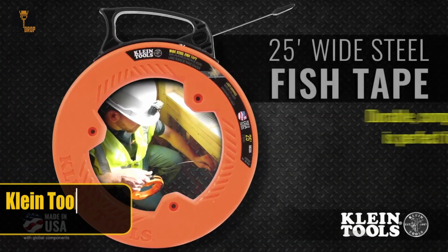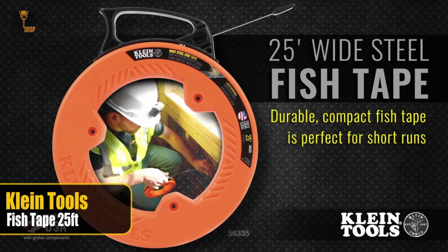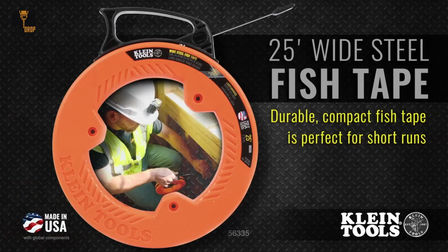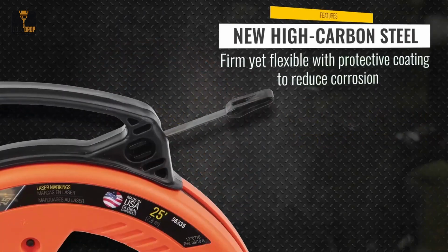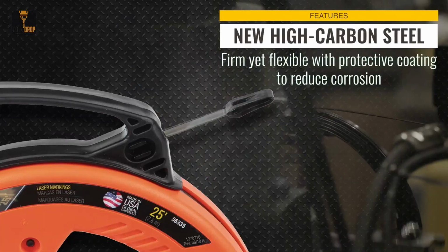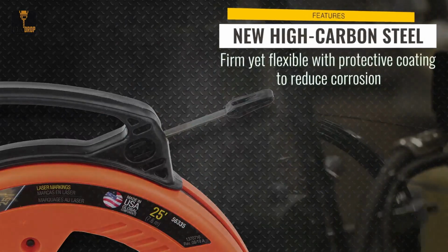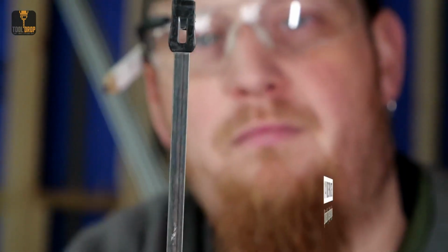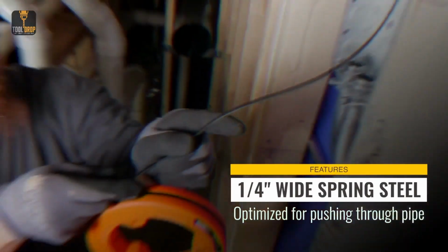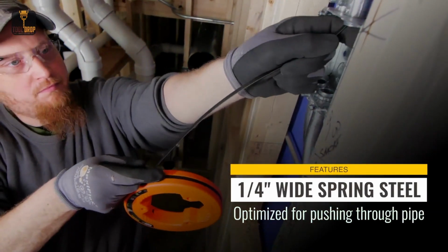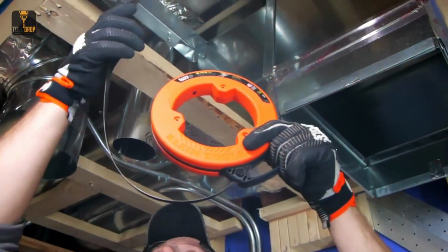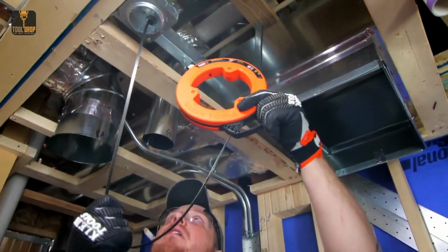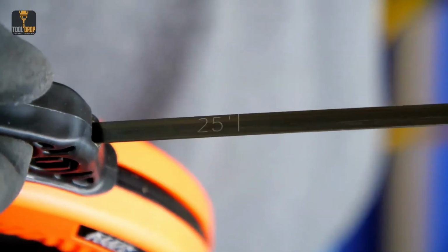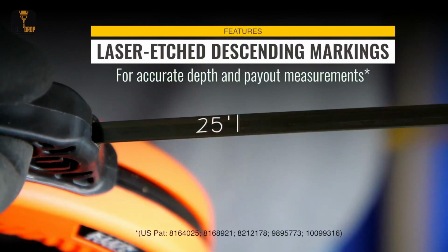Klein Tools 56335 Flat Steel Electrical Fish Tape. 25 feet, $16.97. 2,411 reviews at 4.6 stars. Running new wire through a finished wall without opening it up requires a fish tape. Feed the flat steel tape through the wall cavity from one access point to another. Attach the new wire to the tape at the far end. Pull the tape back through, and the wire follows it through the entire run.